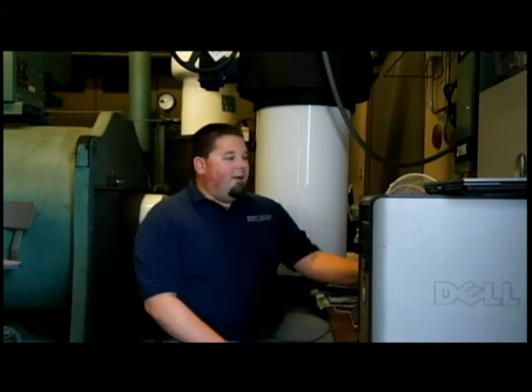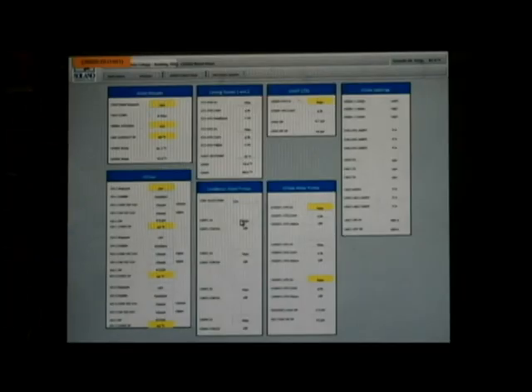When the lag situation comes in on these guys is we have a 45 degree set point on all of them at the moment. If we are not achieving that set point for an allotted amount of time, and all of this is adjustable, then we do call the lag chiller to come on. So if there's a heavy demand, a very hot day here in Fairfield, a lot of chilled water being used out there, then we need to bring up a second chiller so that we can keep up with that demand and actually supply 45 degree water out to these buildings. So that covers just about everything under there.